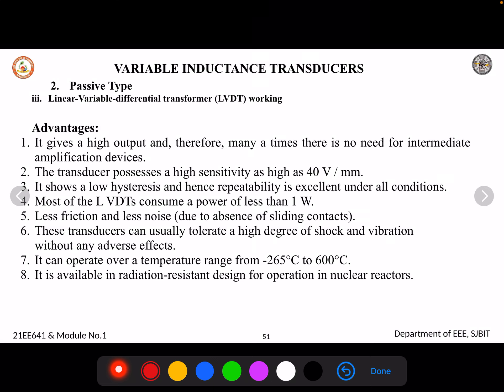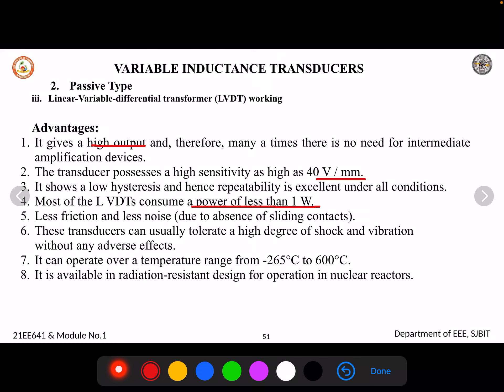Some advantages of LVDT: it has high output and high sensitivity of up to 40 volts per millimeter of deflection caused by mechanical input. It consumes very less power — less than one watt — due to the transformer design. There is less friction and less noise due to the absence of sliding contact; only a movable core is present. It can also operate across a temperature range of minus 65 to 600 degrees Celsius.